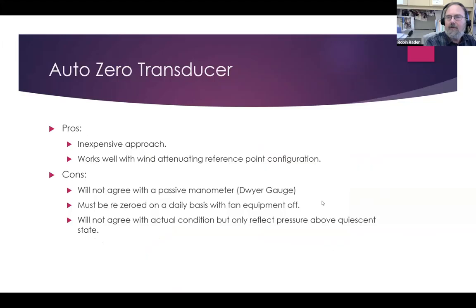You can also buy an auto zero transducer. An auto zero transducer can be set up so that it resets the 0 point every night. So this is a pretty inexpensive approach to this problem. It would work well with a wind attenuating reference point configuration. However, we don't use these things.